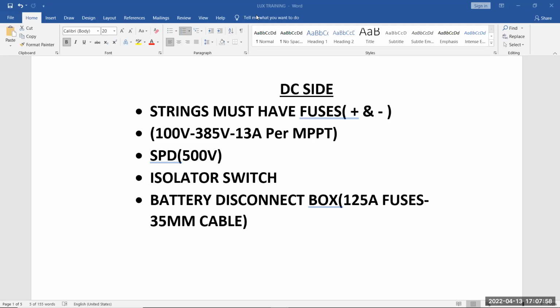So it depends on what's your application. For 2 inverters, 4 mil should be fine, but I'll go rather for 6 mil cables on 2 inverters. And if you have 3 inverters, that's pulling 50 kilowatts. 15 kilowatts, excuse me. 15 kilowatts is roughly going to be around 60 amps. So there I'll go to a higher size wire, like an 8 mil or something like that, depending on the distance.